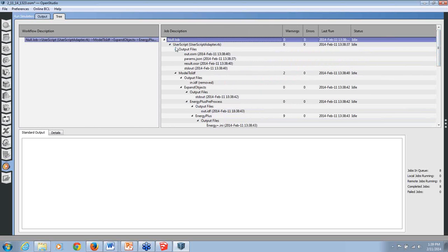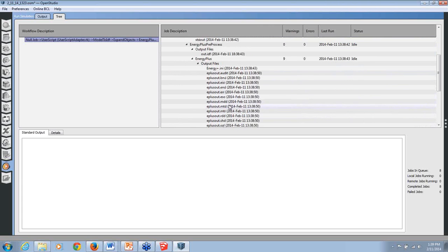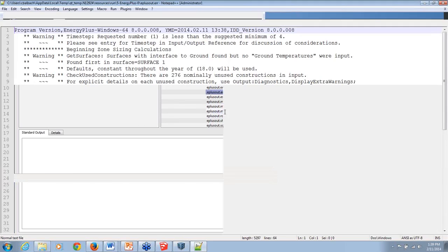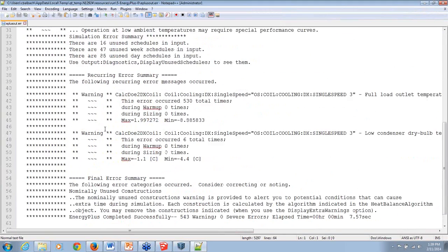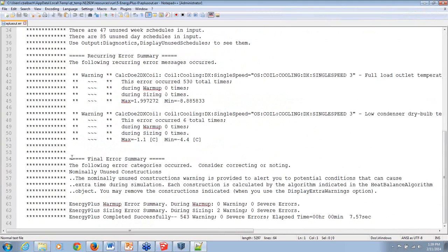You start at the top, you see here that OpenStudio takes the OpenStudio model, generates an IDF model, and eventually runs it. The most important thing here is there's a file. Those of us who use EnergyPlus know this file very well, eplusout.err. We can always look at the file and see if a run crashed, why? Why did it crash? You'll have a severe or fatal error, we figure out why, and we fix it, and then run it.